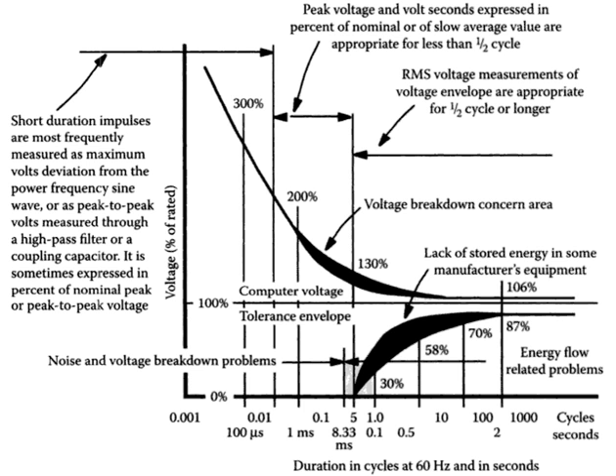It is often useful to think of power quality as a compatibility problem. Is the equipment connected to the grid compatible with the events on the grid, and is the power delivered by the grid, including the events, compatible with the equipment that is connected? Compatibility problems always have at least two solutions. In this case, either clean up the power, or make the equipment tougher. The tolerance of data processing equipment to voltage variations is often characterized by the CBEMA curve, which gives the duration and magnitude of voltage variations that can be tolerated.